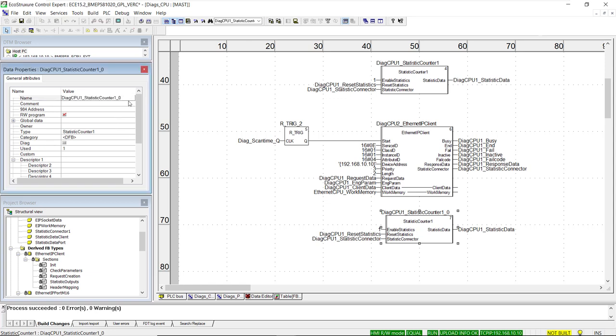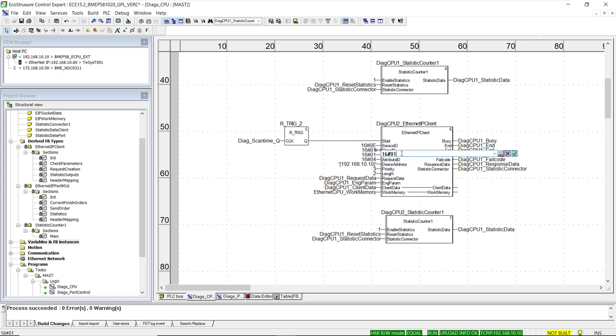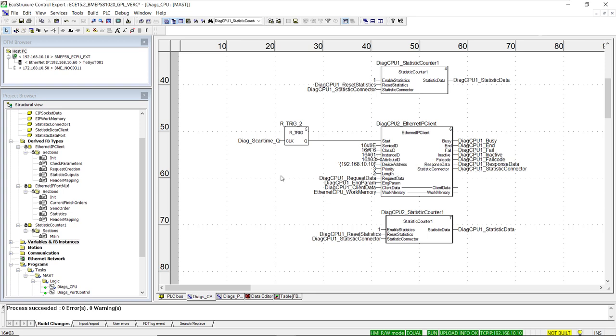Modifying the prefix from DiagCPU1 to DiagCPU2 is not strictly mandatory, but it will be very useful when integrating Control Expert GPL with the general purpose library for Aveva System Platform and OMI. We then update the values and variables connected to the input and output pins. The service ID will not change, but class, instance, and attribute need to be updated as per the documentation to obtain the MAC address of the CPU. Variable prefixes are replaced from DiagCPU1 to DiagCPU2.